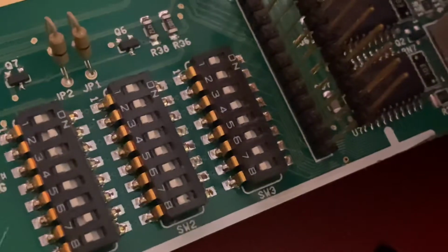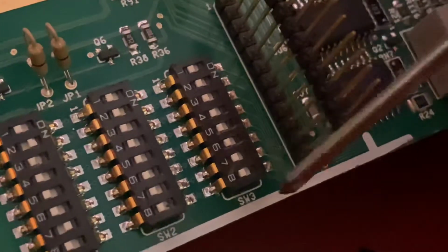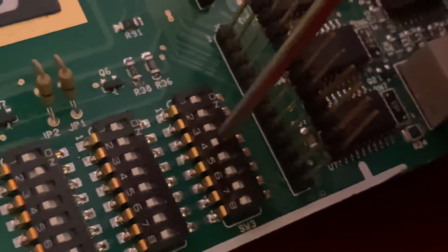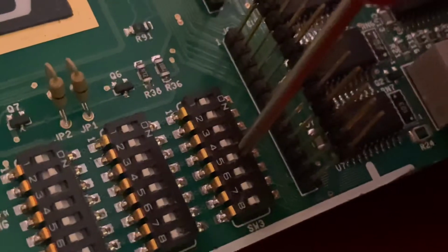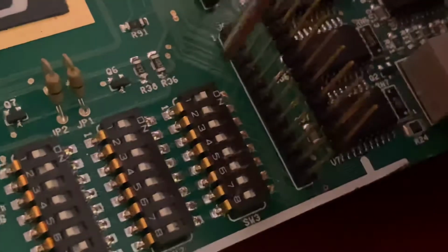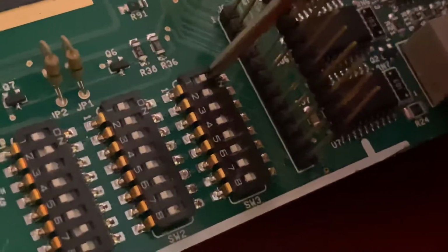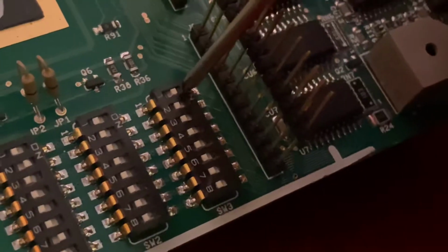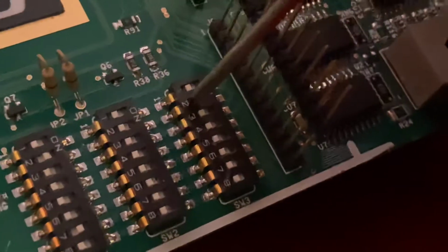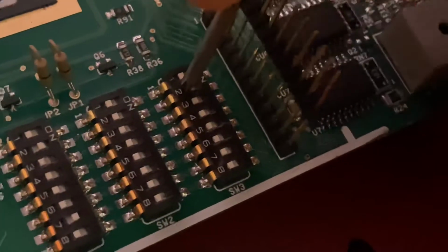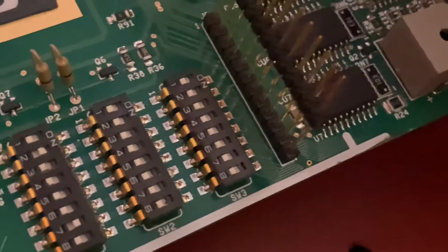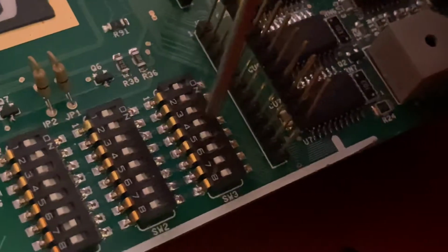Now finally for set 3 here, switches 1, 2, 3, 4 are for NAC 1 and 2: 1 and 2 for NAC 1, 3 and 4 for NAC 2. Switch 1 will make NAC 1 non-silenceable, so if I have a strobe hooked up to that and I have that on, the strobe will keep going until the panel's reset. And switch 2 will just disable it. So if I had to do maintenance work on a NAC, I'd switch that on to disable that NAC, so I can maybe swap it out or something. The same applies for 3 and 4, except that's for NAC 2.